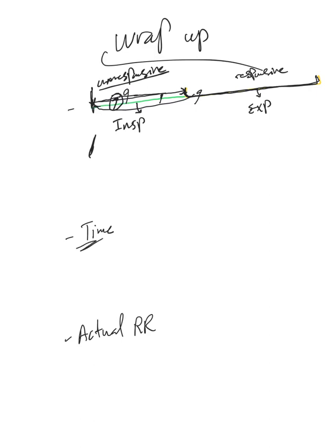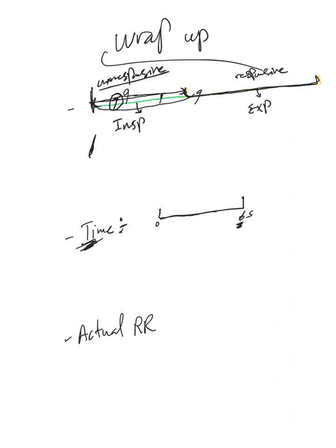The second thing: the ventilator trigger can also be called a time trigger, because it's decided by time. Remember the six second example from the last video. The ventilator will wait for six seconds, and if there's no breath, it will go ahead and deliver a breath. It will reset if there is any patient-triggered breath.